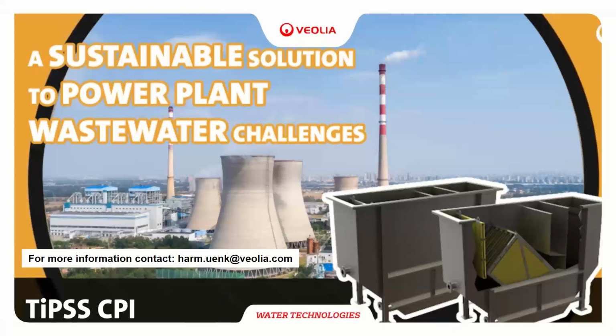Can we use corrugated plate interceptor for other wastewaters as well? Yes, you can. CPI systems are used to separate oil and solids from wastewater in all kinds of industries and applications. It's used in process as well, but also for different types of wastewater. Not only runoff wastewater, but also desalted wastewater or produced wastewater. So yes, CPI separation is based on free oil droplets, but can be used to separate all kinds of particles when there's density difference between the particle and the main fluid. So yes, it can be used in different applications.